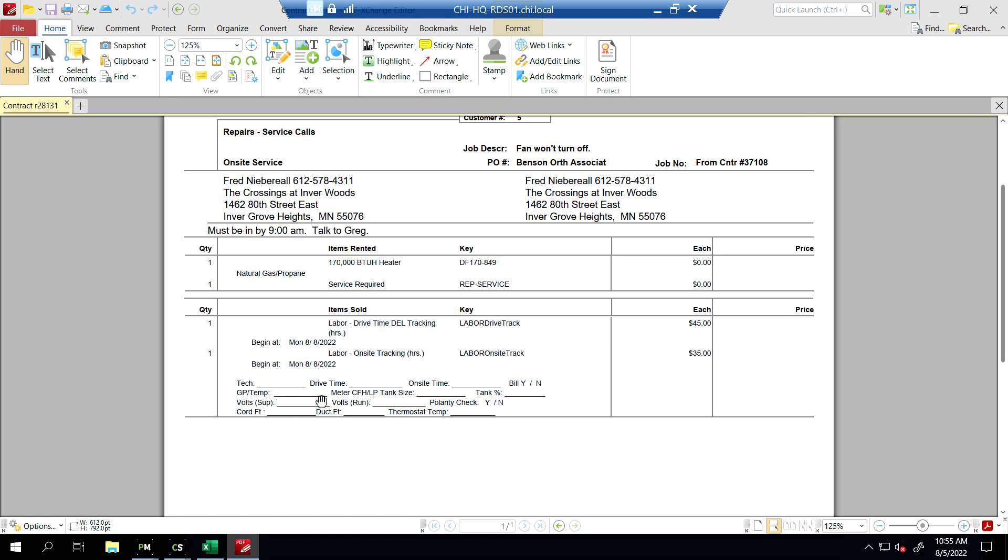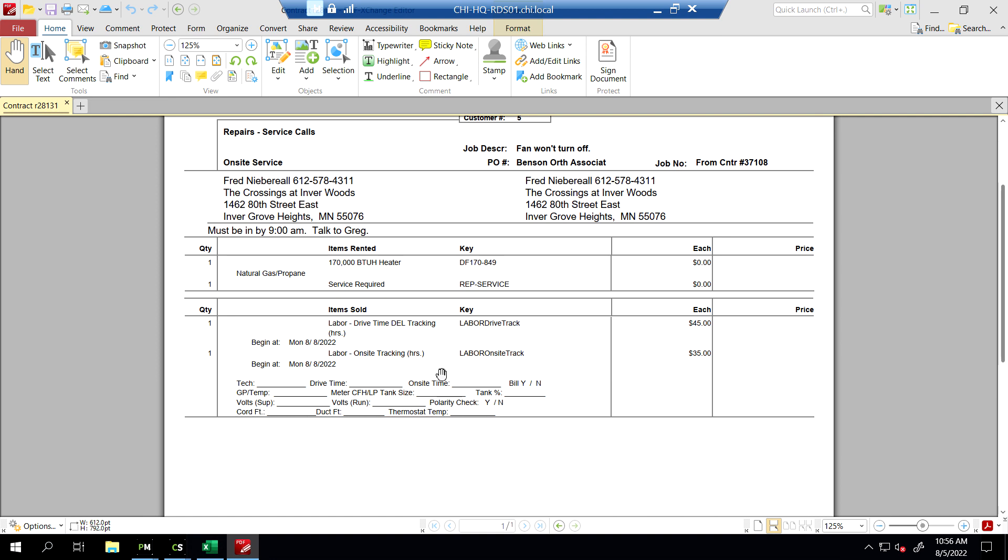You have your supply volts. So we use our volt meter, check the outlet, see if it should be right around 120 volts for the wall outlet. And then we check the heater when it's running to find out, make sure we're at least a minimum of 110 volts. And so they put that information there as well. If they need to check the polarity, certain heaters you have to check the polarity on. They say yes or no for that.